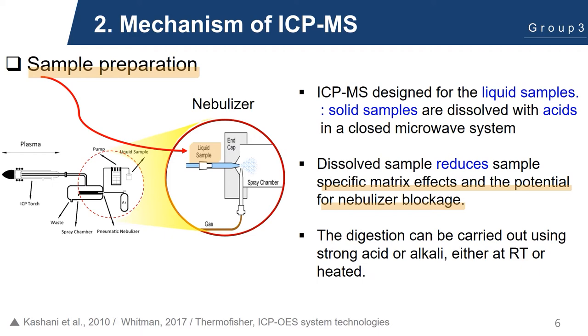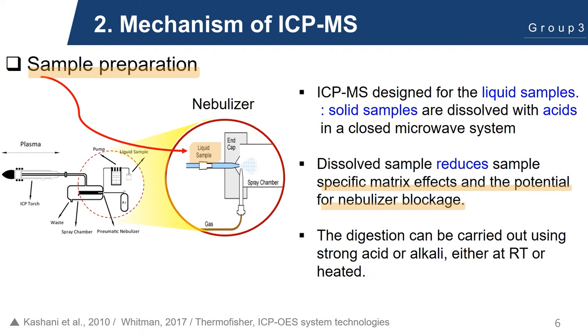The nebulizer is the place where aerosolization of samples occurs. A sample vial pumps the sample into a nebulizer, which is then mixed with argon gas to form an aerosol — a suspension of liquid samples in an argon gas matrix. While traveling across the cooled spray chamber, larger aerosols are selectively removed by gravity, and fine aerosols are introduced into the hot plasma. This is necessary because plasma is inefficient at dissociating large droplets.